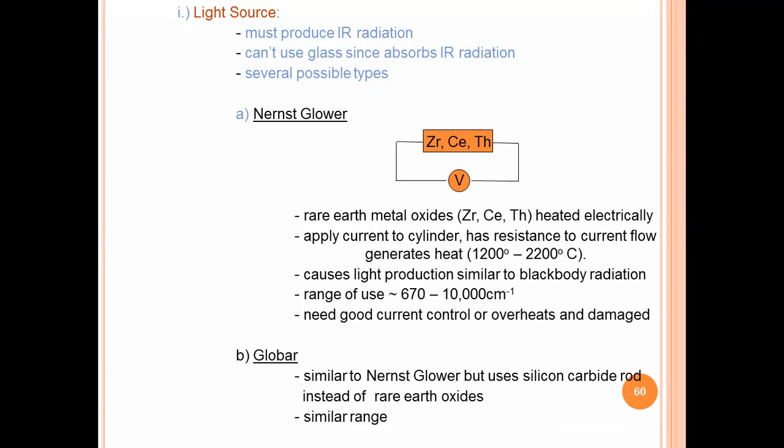If these metal oxides are heated externally electrically, it generates heat or radiations and causes light production similar to blackbody radiation in the range of 670 to 10,000 per centimeter wave number. It needs good current control or overheats.